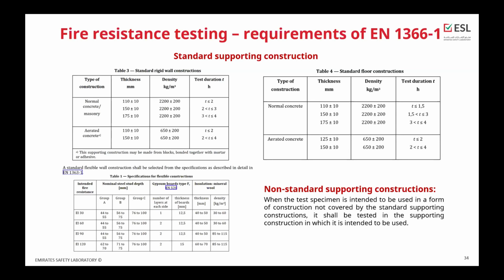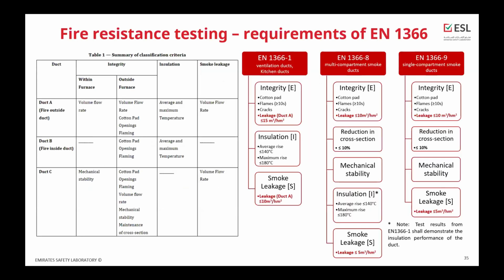However, if you do the test in a concrete wall, you will not get AAC and flexible. So this is something which is unique for the EN standard. However, if there is a project-based separation and a specific design which is not listed as a standard supporting construction, and you test the duct passing through this specific wall, you are linked to this specific wall. So here we can see the comparison and the summary of the classification criteria for EN duct.